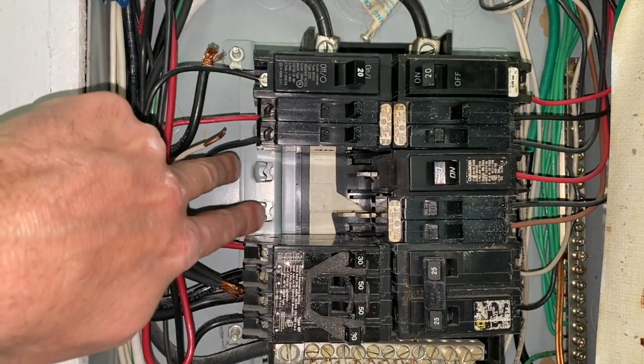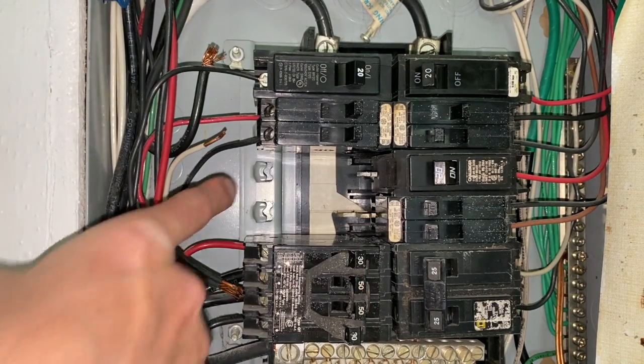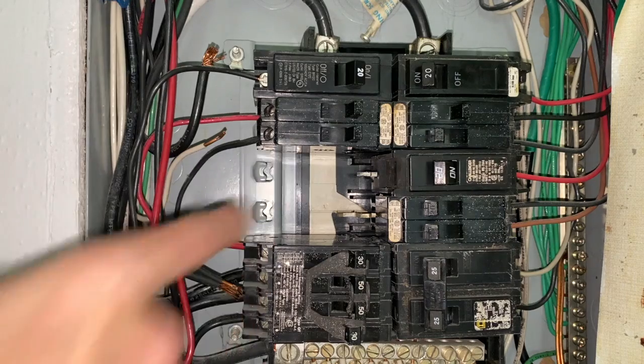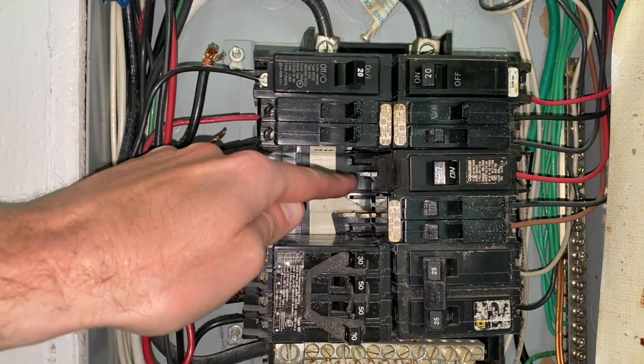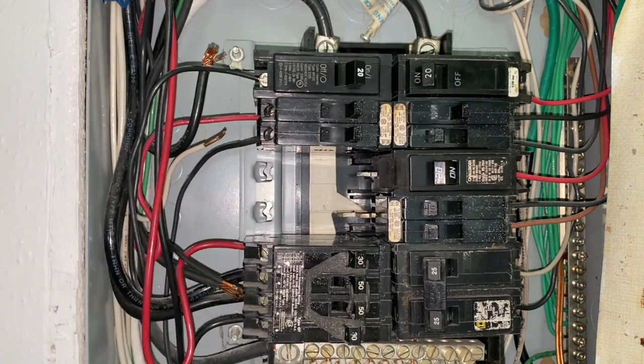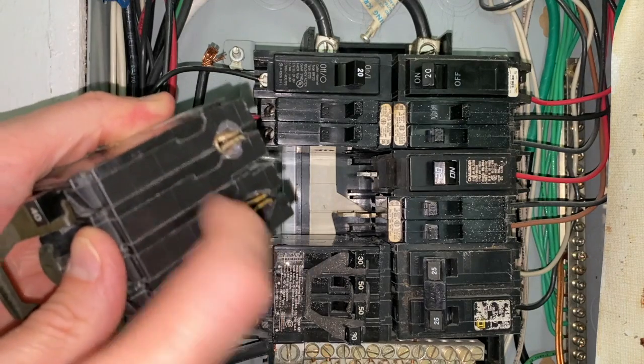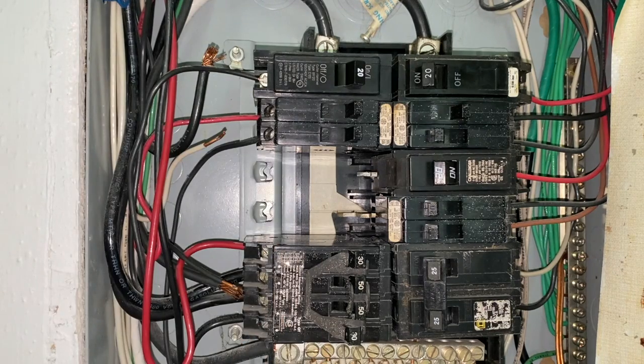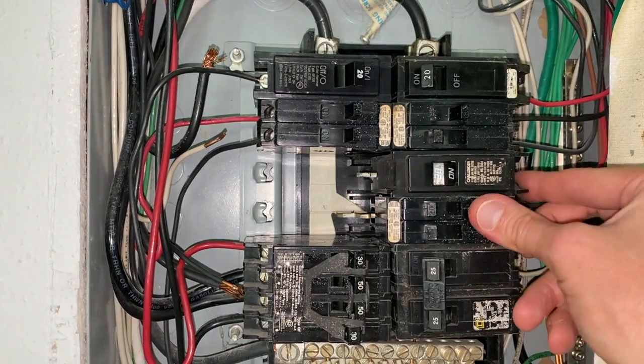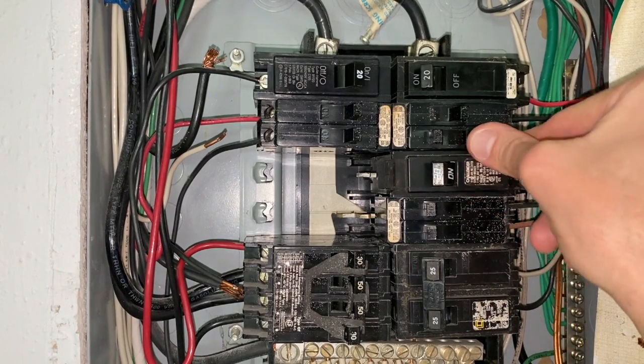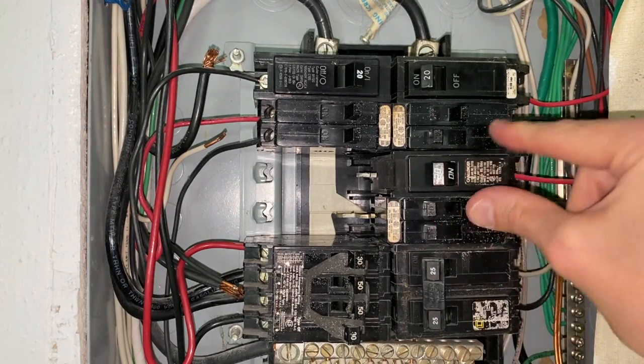And there are the two inner hooks that I was talking about that again have no relation to electricity. However, the inner prongs there, you can see the electrical contacts, one on top, one on bottom. That is what the inner portion right here of the breaker feeds into and completes the electrical current. And again, just ensure that any breaker that got offset or shifted as I remove that one is properly reset and positioned.